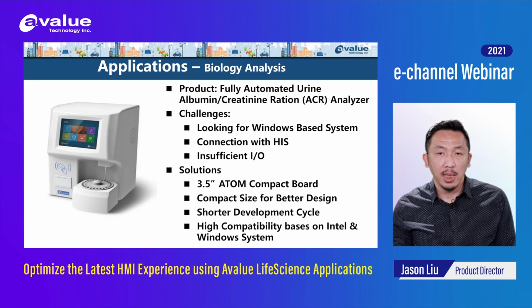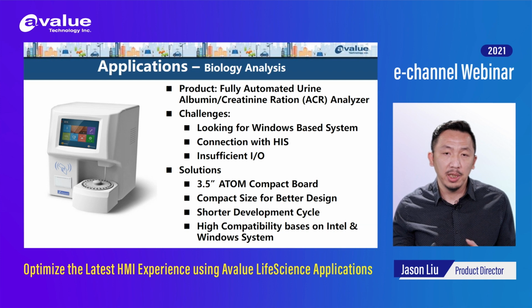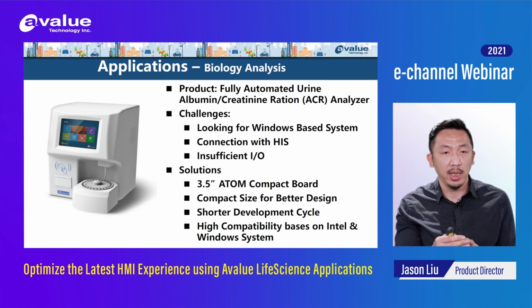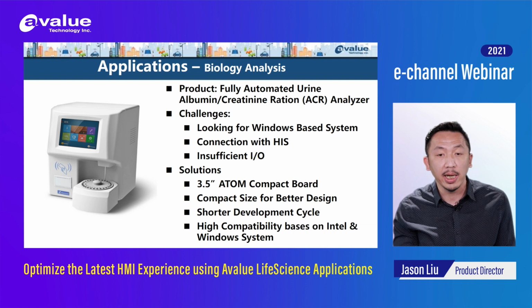And the next one is the fully automatic urine analyzer. For this one, they want to use Windows 10 based products, because they need this system analyzer to connect to the hospital HIS system, so they can download a patient's data directly to this machine, to match the analyzed data with the patient data.